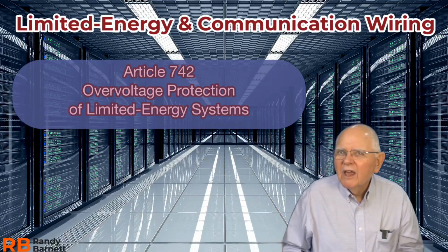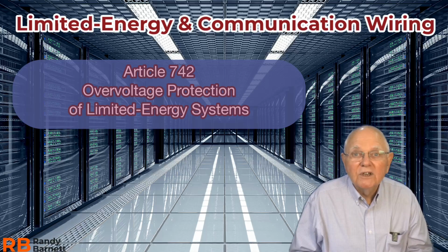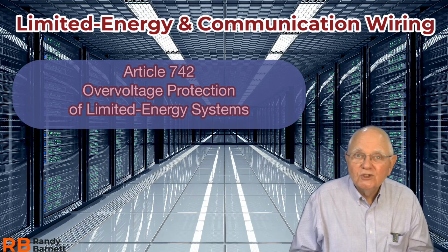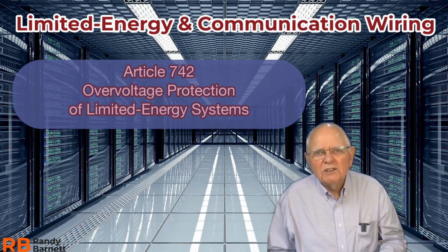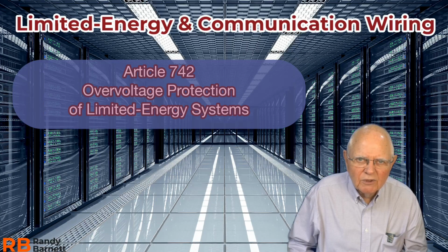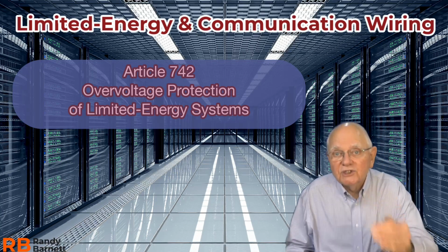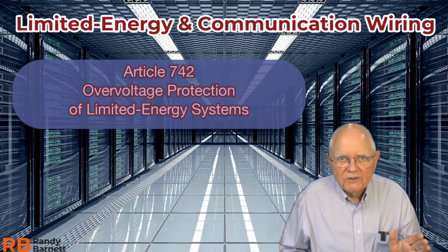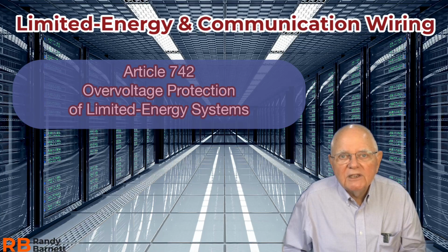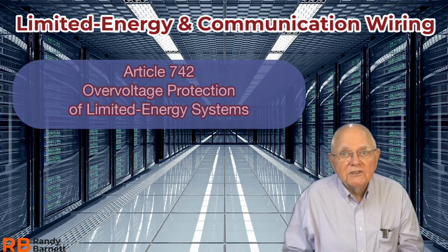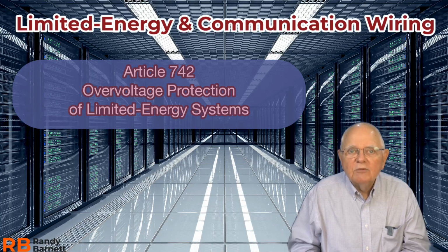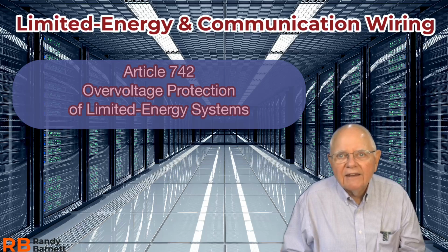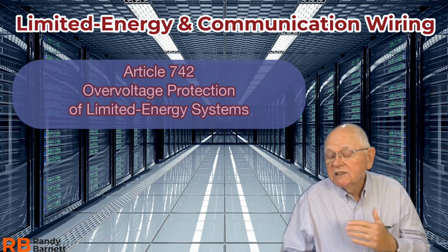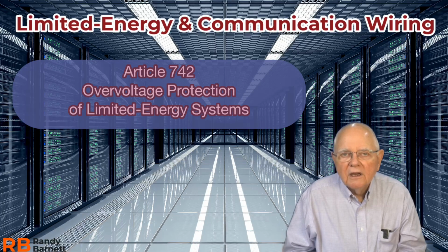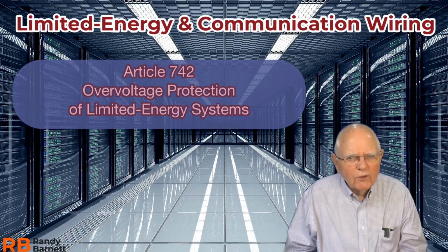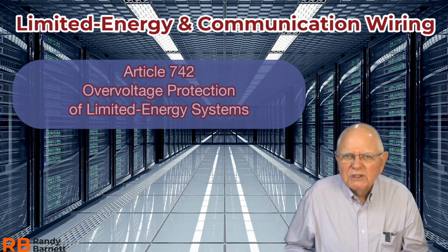Article 742 then, overvoltage protection. Overvoltage protection of limited energy systems. Another very short article. 742.10 talks about primary protectors, .20 about secondary protectors. And then .30 talks about how to install these protectors. What's the protector and all of that information about? Well, take a look at the informational note. There are informational notes that explain primary and secondary protectors. For lightning strikes in communication circuits, we use primary protectors. For voltage surges and things like broadband systems, probably secondary protectors.